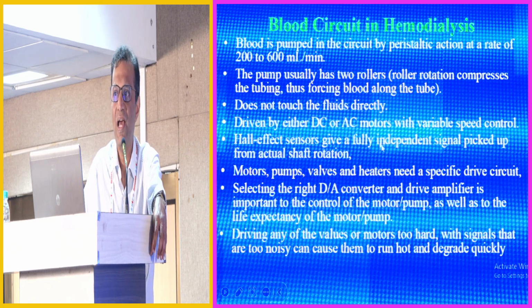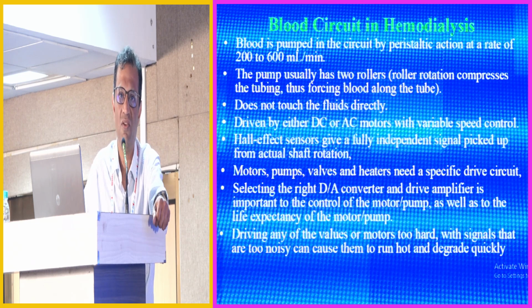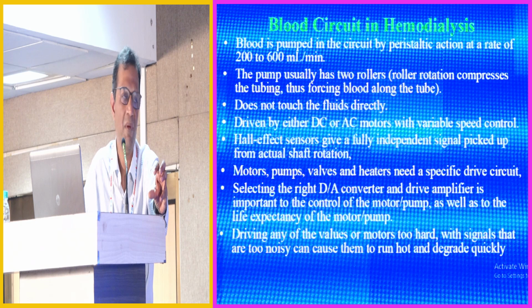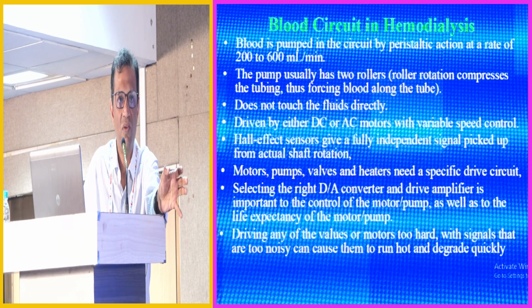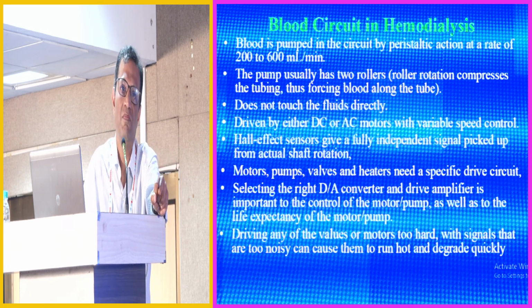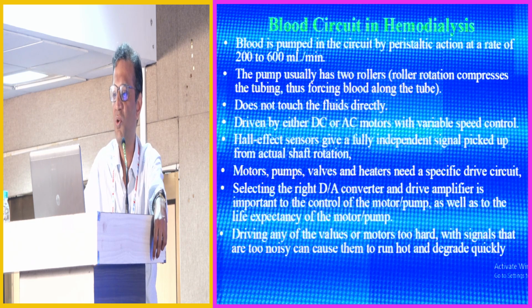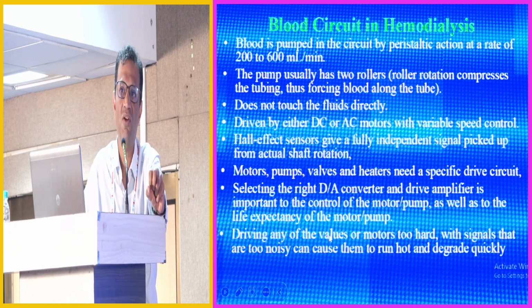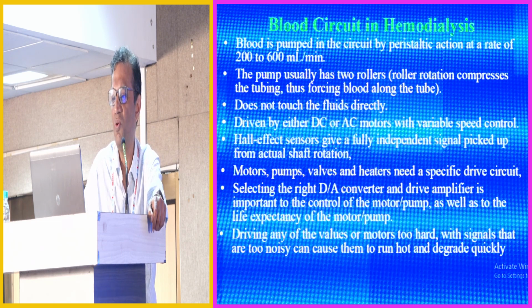The blood pump of our dialysis, we've just heard that the ECMO pump is a centrifugal pump. Now, the centrifugal pump means that the blood enters the body, the housing of the pump. In contrast to that, our machines use a roller pump in which there are 2 or 3 rollers rotating, which squeeze the pump segment of the blood tubing. That creates a vacuum, and as the roller moves forward, that vacuum sucks blood and fills up with blood coming from the vascular access. The amount of blood flow is a function of the volume of the pump segment and the rotational speed of the motor. And there is a Hall effect sensor which feeds back to adjust the rotational speed of the motor.